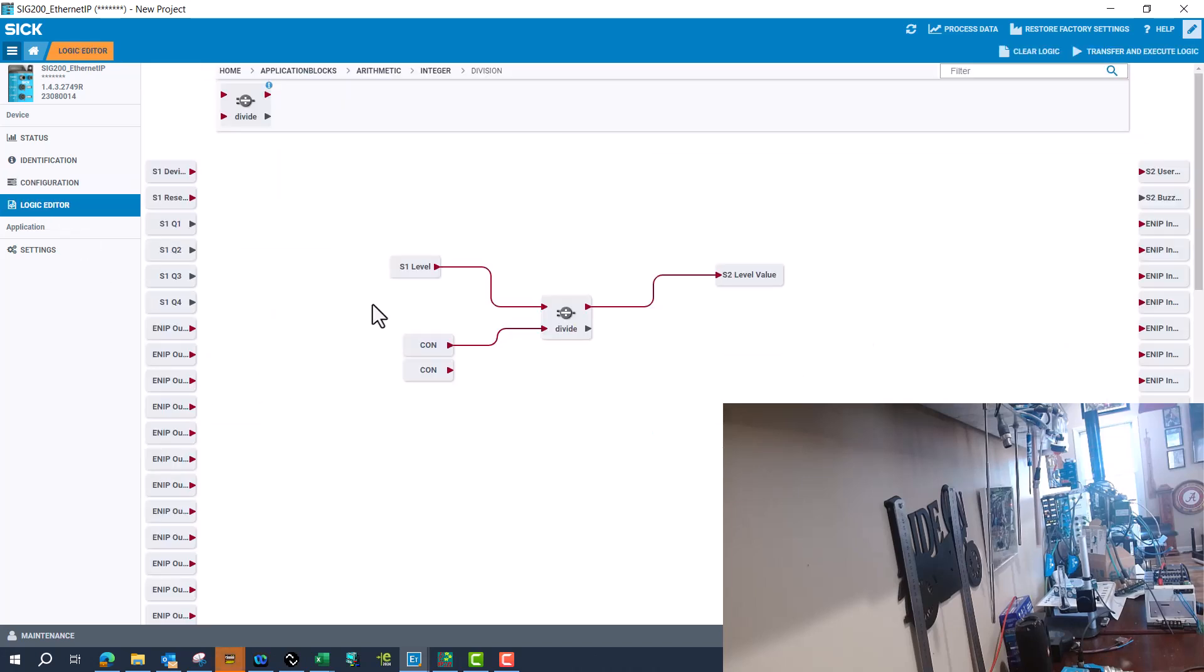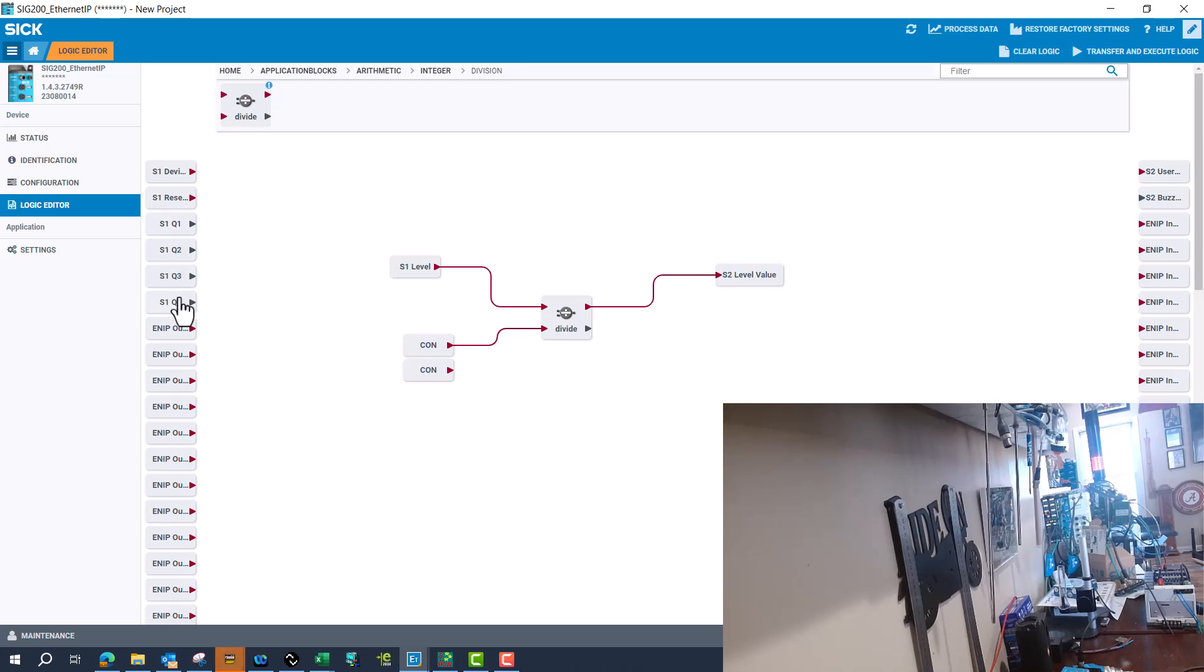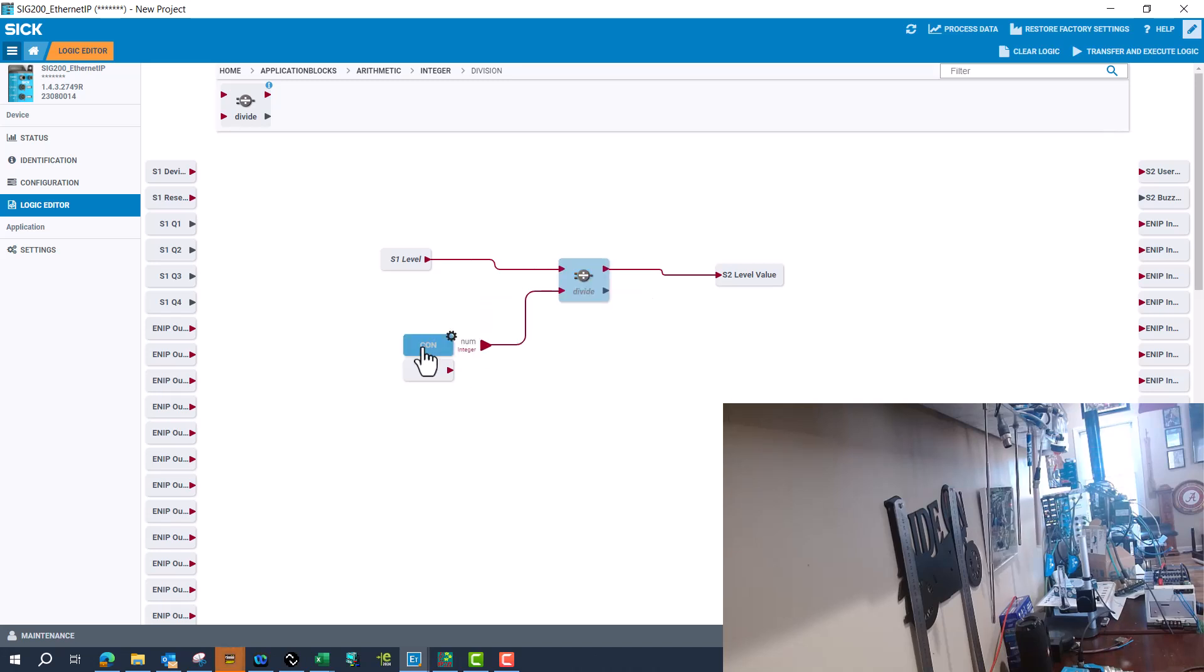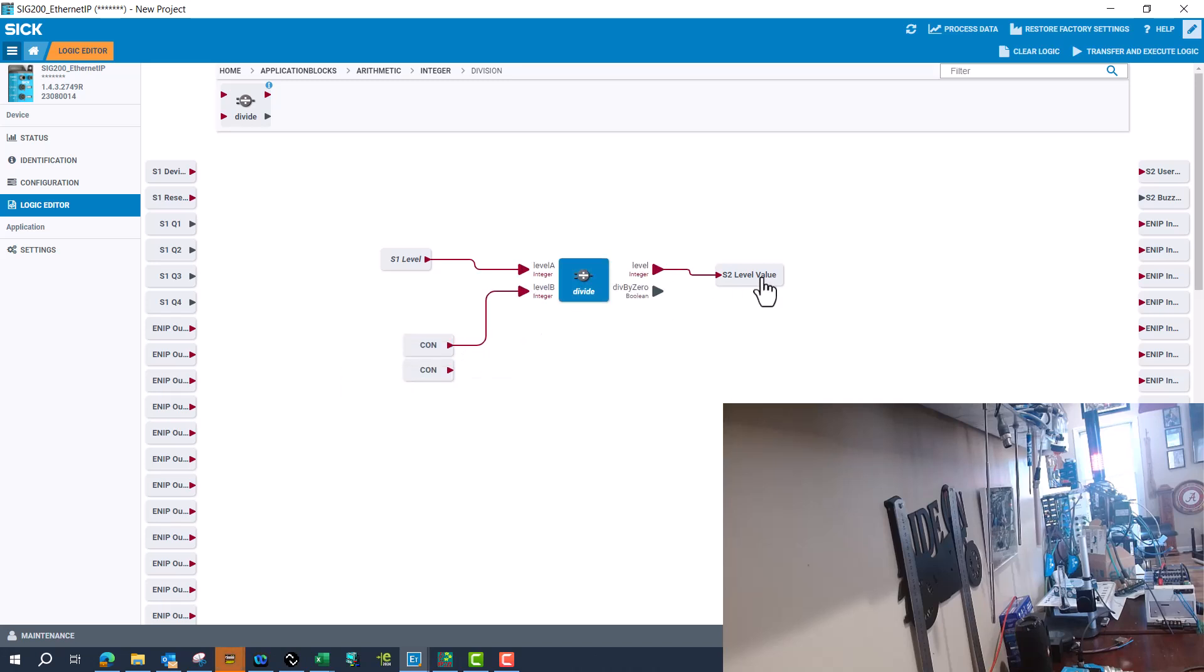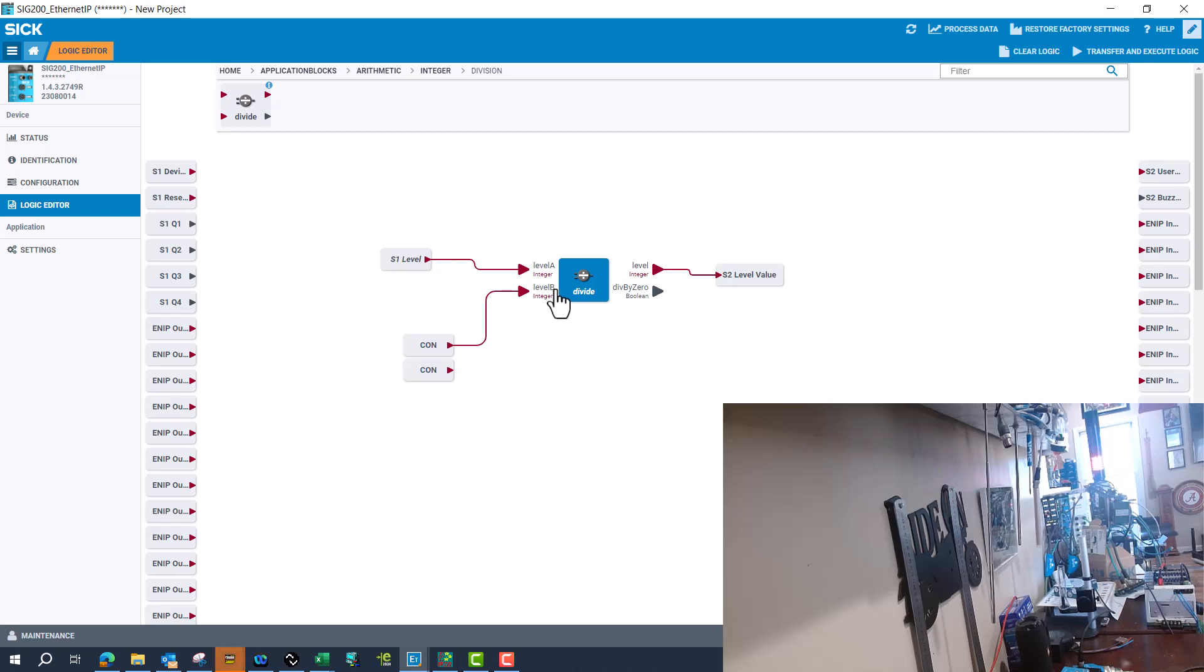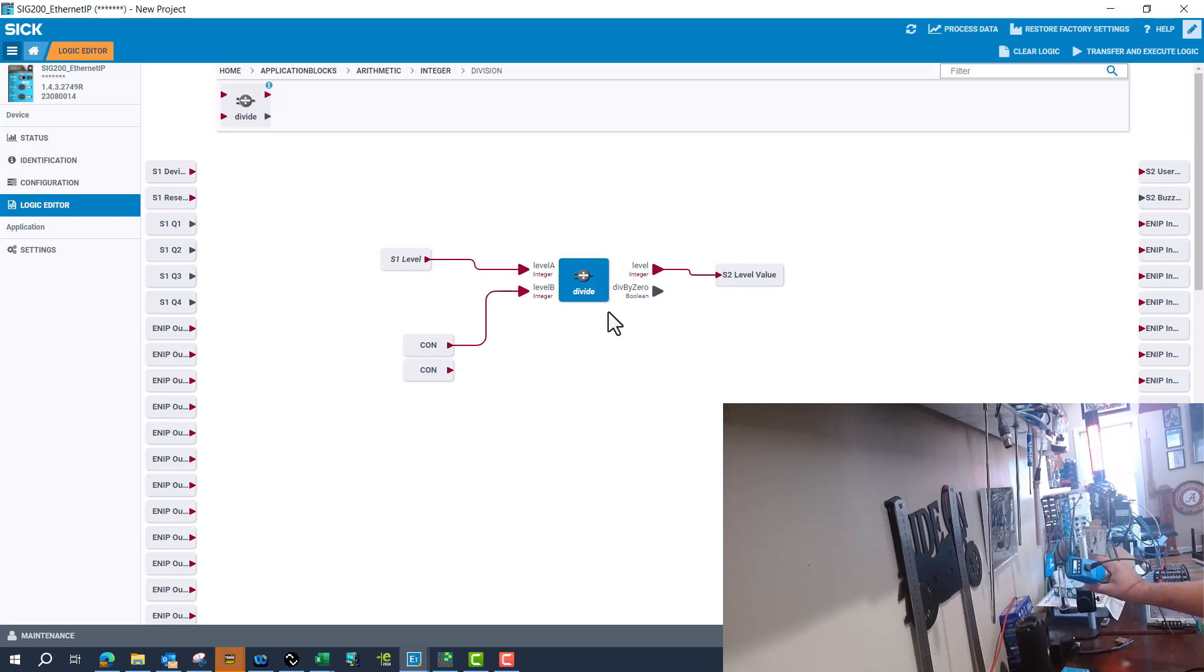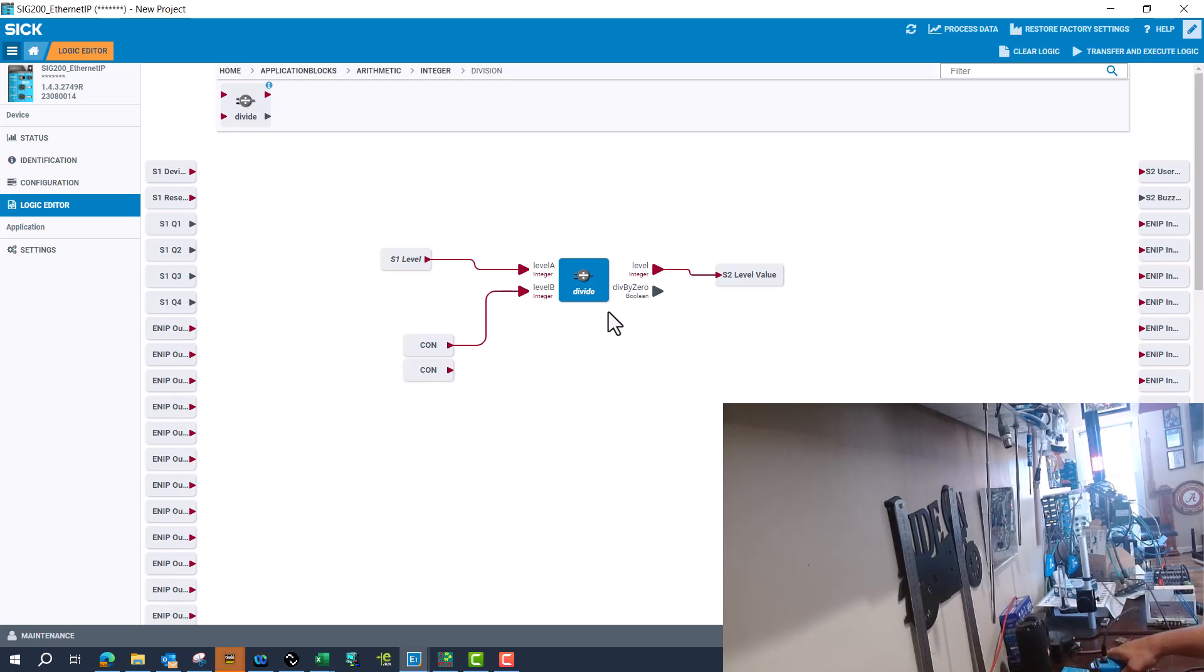So now, if I come to logic editor, once I hit the clear logic refresh, it'll give me all these different things of inputs and outputs. You set out and get Q one through four out of the LFP here, also if I want to. But, so what I did is I took the LFP, which is on port one or S1, and I took that into a divide because I need a percentage for the SLT. All I did was to come here and I gave a divider of two. And that gives me a percentage. Since I'm 200 millimeters, worth of what this is set for, I divide it by two. So if I'm at 100%, then I should be at 200 on the LFP. If you see the lights all the way up. If I take my hand off, I'm going to go about 64, which is about 30% is what you can see there.